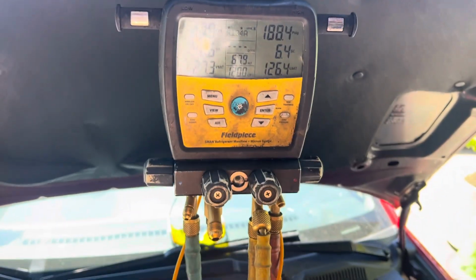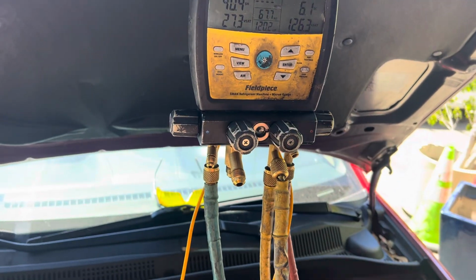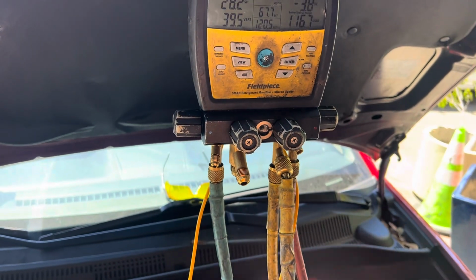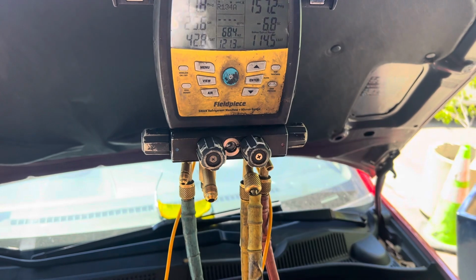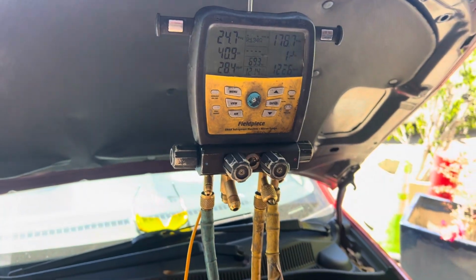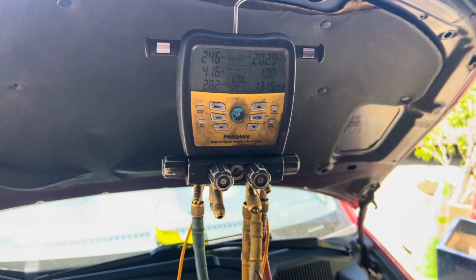So that's an option. Now, if it was a compressor burnout, it's not an option. You change the expansion valve every time. I'm talking about a black burnout with burnt oil and metal flakes and everything like that. Not even an option. New everything. No options available on that one if you want warranty. If you don't want warranty, go to the cheap guy down the corner who will just throw on a compressor on a burnt out system with metal flakes on it, change no parts, and see what you get for that cheaper price. See a lot of those on YouTube. All right, guys, I'll see you later.